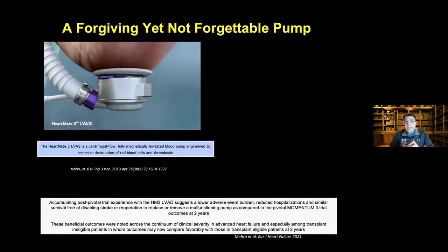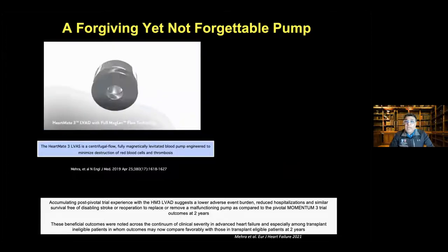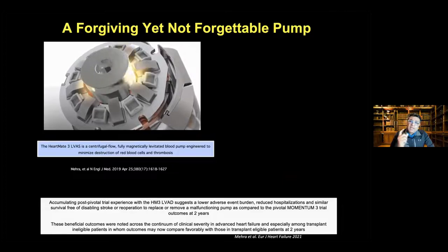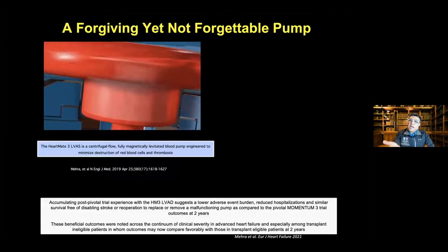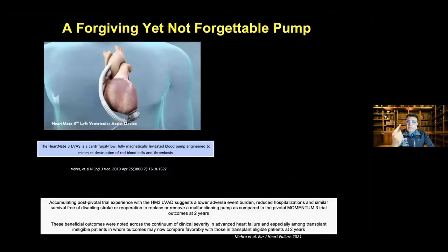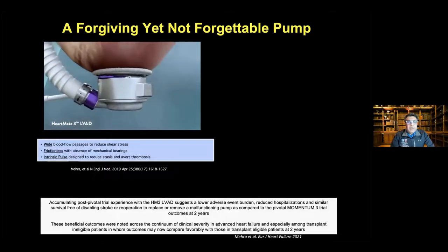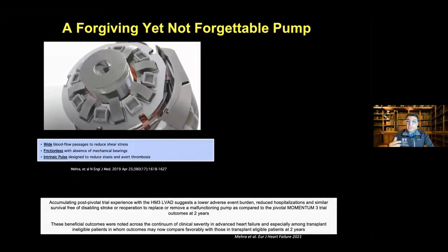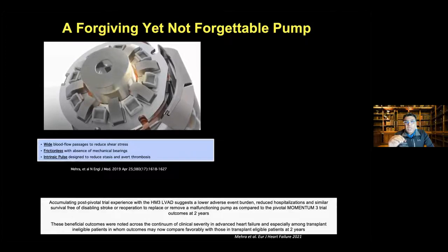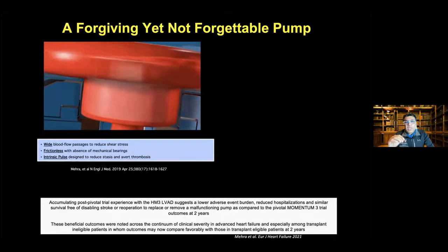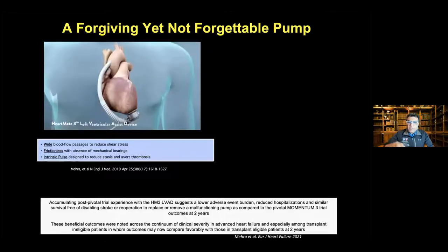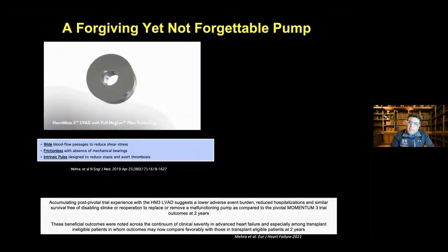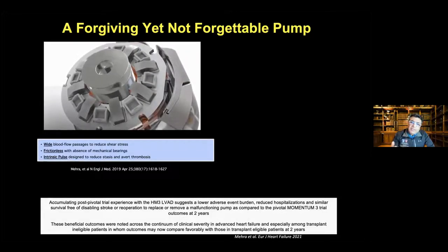The device that is commercially available and is now the only predicate device for widespread use is the HeartMate 3 pump. This pump was specifically engineered to be fully magnetically levitated in terms of its rotor, so it does not require hydrodynamic elevation — the rotor can move in air. It has very wide blood flow passages, eight times more than previously commercialized devices like the HVAD, allowing low shear stress. It is frictionless and built with an intrinsic pulse algorithm.